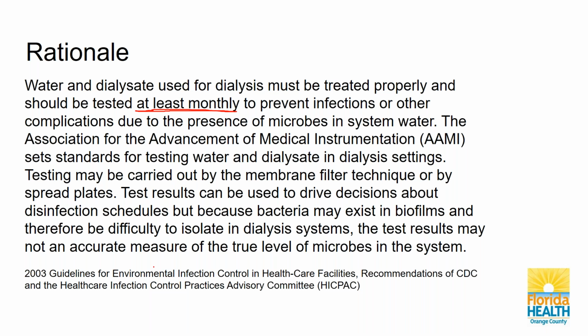Testing may be carried out by the membrane filter technique or by spread plates. Test results can be used to drive decisions about disinfection schedules, but because bacteria may exist in biofilms and therefore be difficult to isolate in dialysis systems, the test results may not be an accurate measure of the true level of microbes in the system.